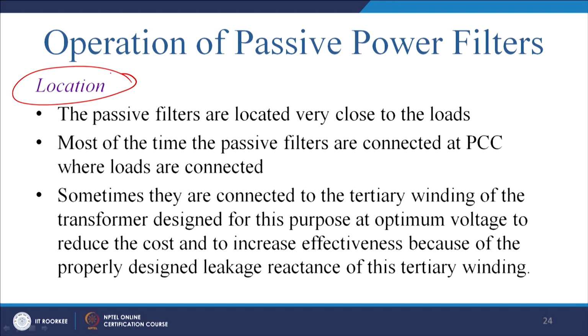It is a multi-bus system, and you require to run the load flow study. From the load flow study, you require to find the saddle point where the strength of the fifth harmonic is maximum in a particular bus, and in that bus you will connect the particular filter. In this case, we are assuming a single line, only single bus system.